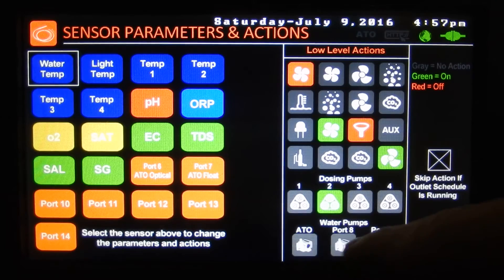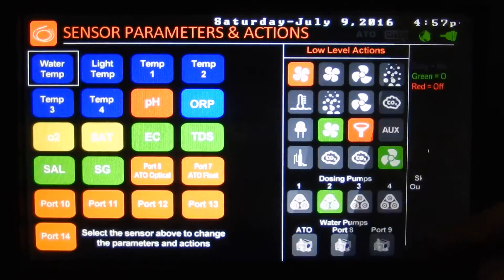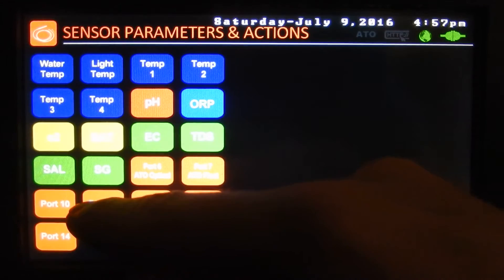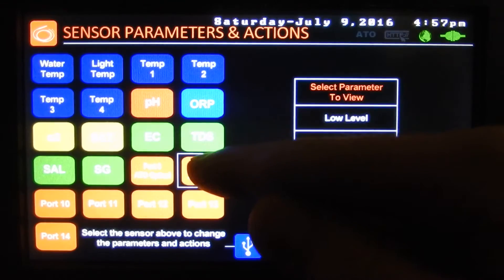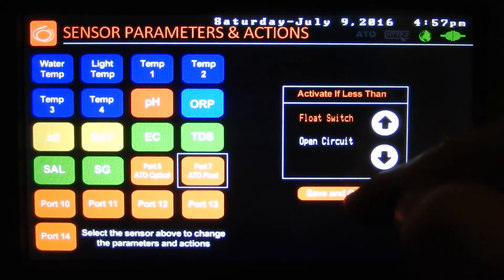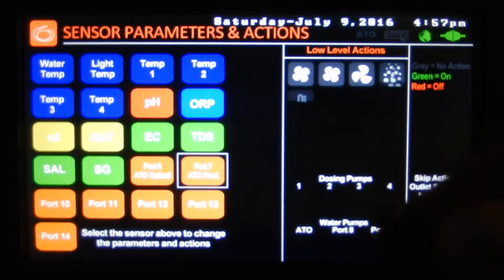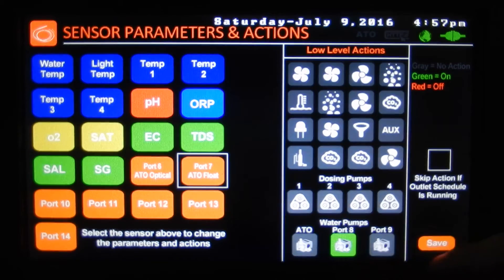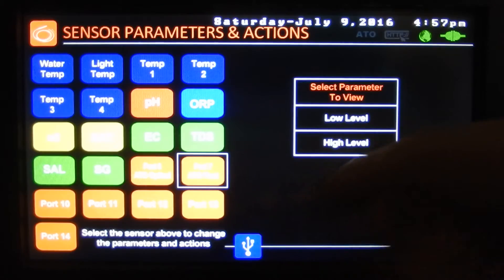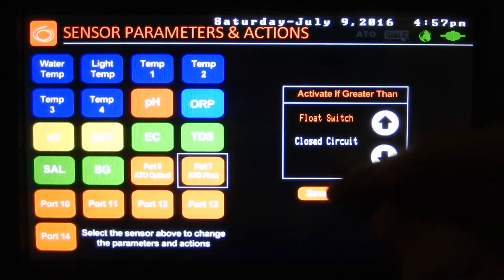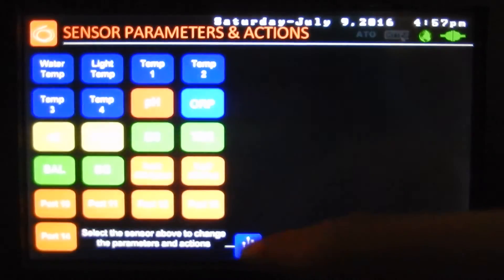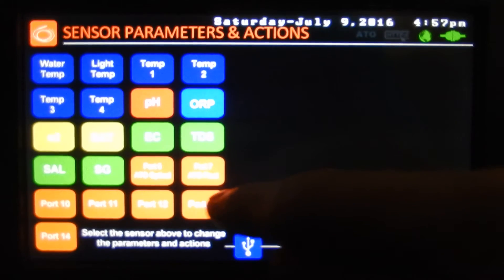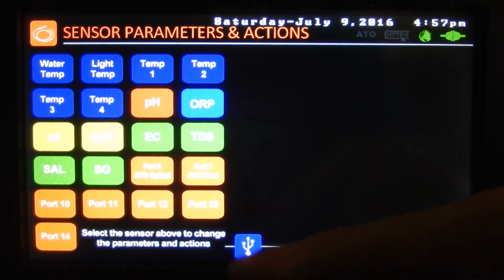So here you can set any kind of rule — start up pumps, use different sensors like our ATO float sensor. The low level — if it's an open circuit, what do we want to do? We want to start that pump. And if it's a closed circuit, we want to stop the pump. So if we're going to start the pump, we want to make sure we create a rule to stop it or it won't stop.